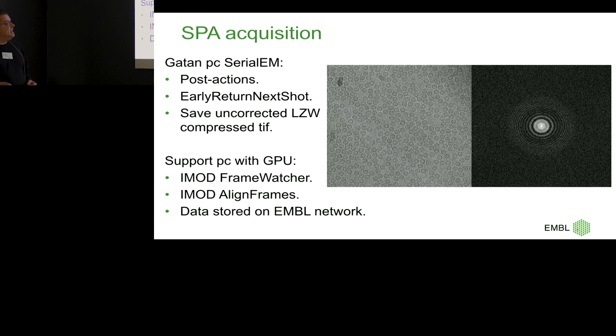But in the end, I want to see something. Because SerialEM comes from David Mastronarde, who also writes IMOD, I put a slightly bigger support PC in — FEI doesn't care if you put a different PC in, as long as it's Windows 7 or 10 and the rapid stuff works. So a slightly bigger PC with one GPU, on which we installed IMOD. You just download IMOD, it's free, it installs itself, and then you have Frame Watcher, which can see the frames that SerialEM has written on the Gatan PC.